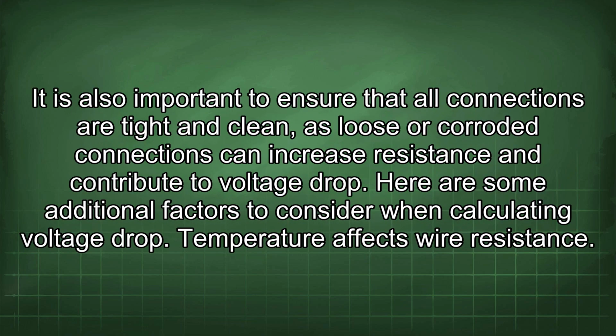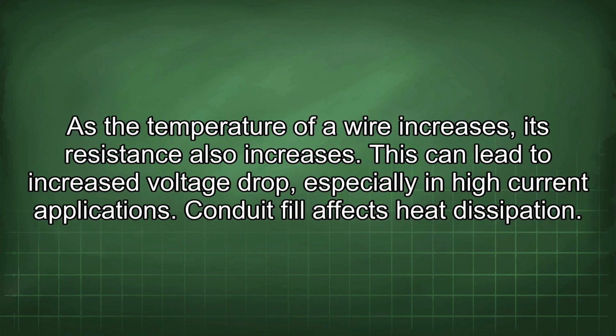It is also important to ensure that all connections are tight and clean, as loose or corroded connections can increase resistance and contribute to voltage drop. Here are some additional factors to consider when calculating voltage drop. Temperature affects wire resistance. As the temperature of a wire increases, its resistance also increases. This can lead to increased voltage drop, especially in high current applications.